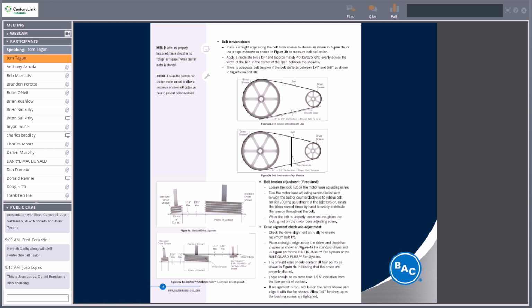Next page in the O&M is a quick guide to direct you on how to check the belt tension. 75% of the time when these towers get started up in the field, they're factory set, but over time the belts will wear, and there are requirements to check the belt tension and a pretty simple adjustment technique. Also, you can see, it's tough to see, but the drive alignment, you can see how the sheaves are supposed to be in alignment, which may indicate some issues with bearing assemblies.